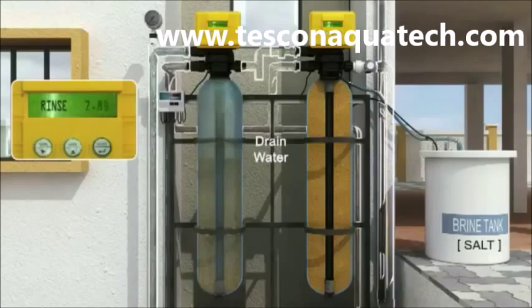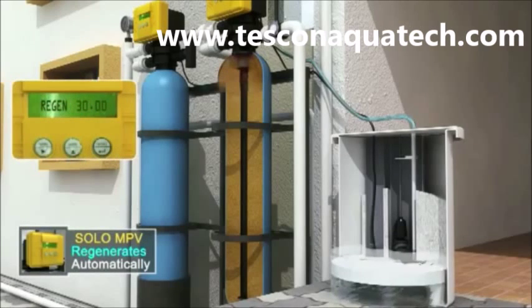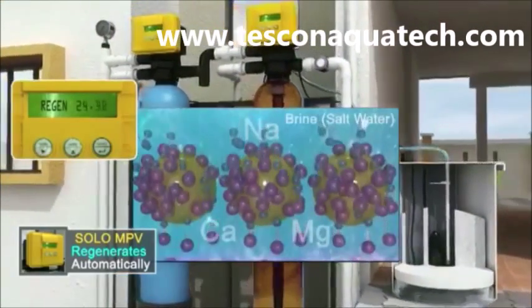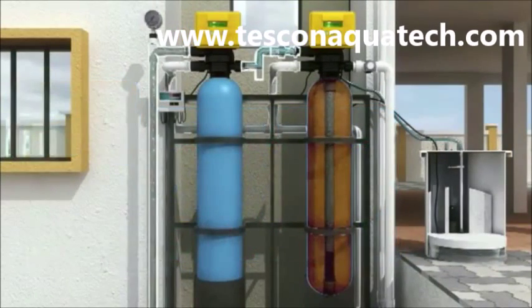Next, it initiates an automatic rinse during which the sand bed settles down and water continues to go to drain until clean water emerges from the filter. At this point, a signal goes to the next SOLO MPV to start regeneration of the softener. Salt solution from the brine tank passes downward through the resin bed and a reverse reaction takes place, where the sodium is replenished and the hardness is removed and goes to the drain.